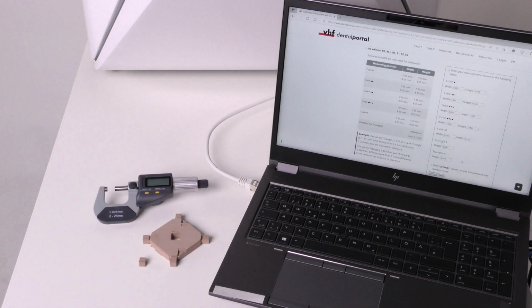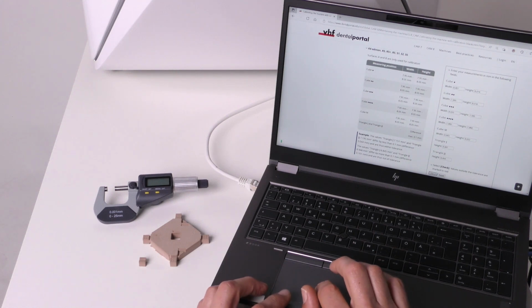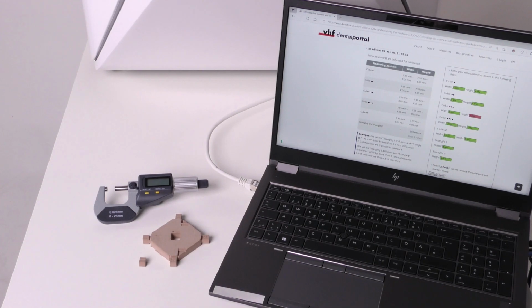After you have determined all the required measurements, check whether the measured values lie within the specified tolerance range or not. For this, select Check. Your measured values are checked against the tolerance ranges. Values outside the tolerance are marked red. If a measured value is out of tolerance, a recalibration of the machine is recommended. In this case, proceed directly with part 3 of 3 in this video series, Calibrating Your Machine, which is linked in the video description below.